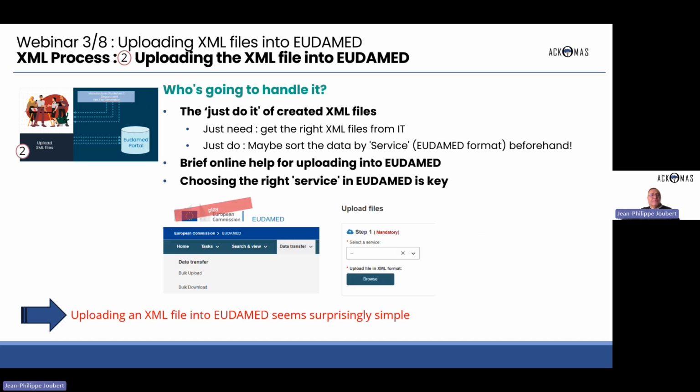Okay. The second step is uploading the XML file into EUDAMED, assuming it has been correctly created or built with the support of an external specialized third party. Notice that in this latter case, the third party is not responsible for the publication of your data. Okay, so let's go ahead and assume your data is flawless and you have unwavering faith in the XML file created by the third party provider. After all, what could go wrong?